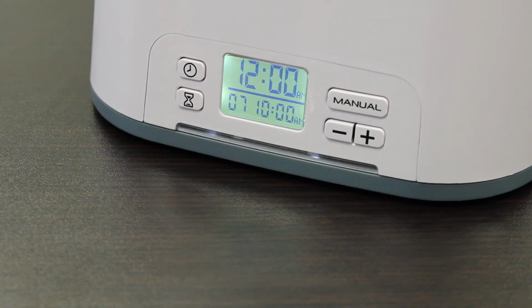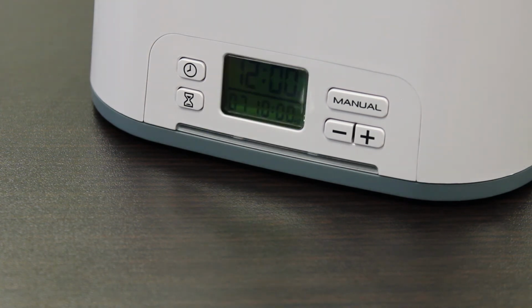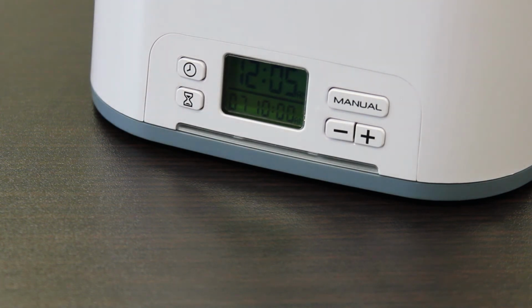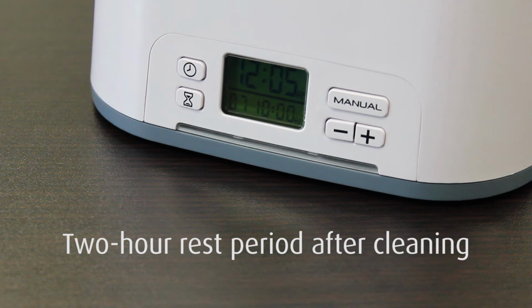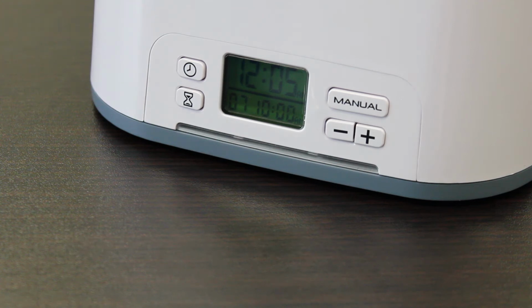Next, we will set the duration of the cleaning cycle and the cycle start time. Please keep in mind when selecting the cycle start time that a 2-hour rest period is needed before you can use the mask and machine. The SoClean comes preset to start a 7-minute cycle at 10 a.m. every day. Change these settings by pressing the hourglass button.